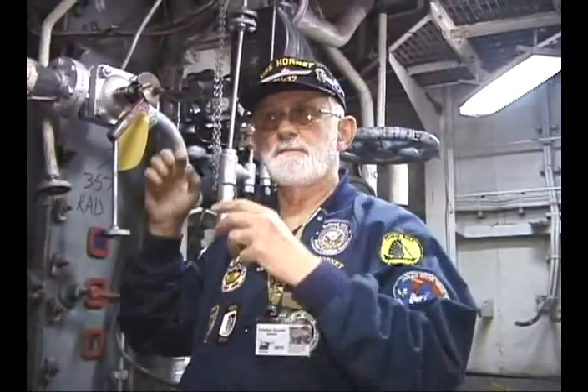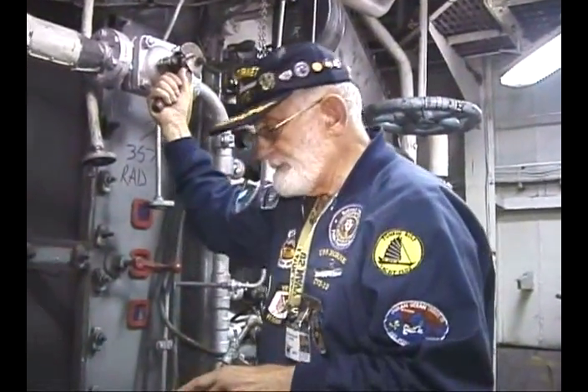Now, Navy Standard fuel oil was a black oil, and you still had to heat it to get it to burn properly. You'd heat it up to about 350 degrees Fahrenheit, and it was a dirty oil, and it left a lot of soot on your tubes. So every 600 steaming hours, and that doesn't take very long when you're steaming 24 hours a day, you have to secure your boiler, let it cool, take all the side panels off, and go in with big steel rakes and brushes and scrape the soot remaining off the tubes. And it takes your nice clean fire room and turns it into a trash pit. It's awful.